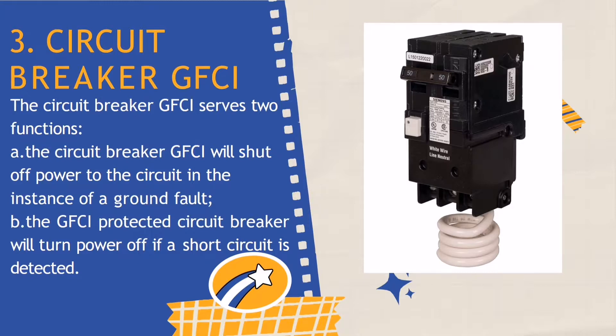GFCI circuit breakers protect the entire circuit. They are installed in the service panel or breaker box, adding GFCI protection to the entire circuit including the wiring and all devices and appliances connected to it. In cases where GFCI and arc fault circuit interrupter protection are both required, there are dual-function GFCI and AFCI circuit breakers that can be used. GFCI circuit breakers are more practical in situations where all outlets on a circuit require protection, such as a garage workshop or a large outdoor patio. However, they carry a higher cost, so installing a GFCI outlet at the first outlet on the circuit may be a more economical option.